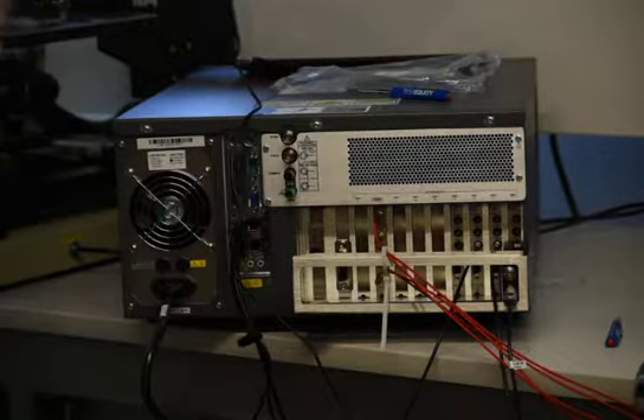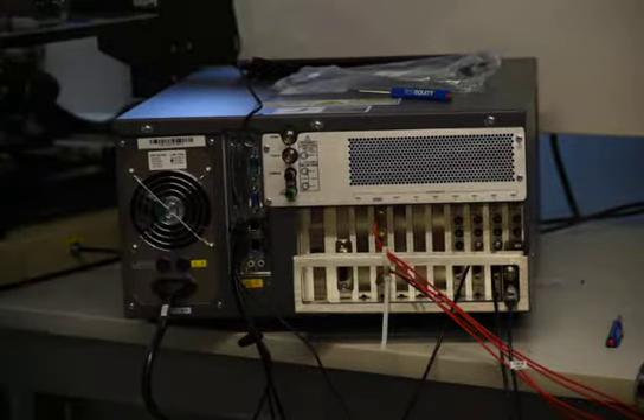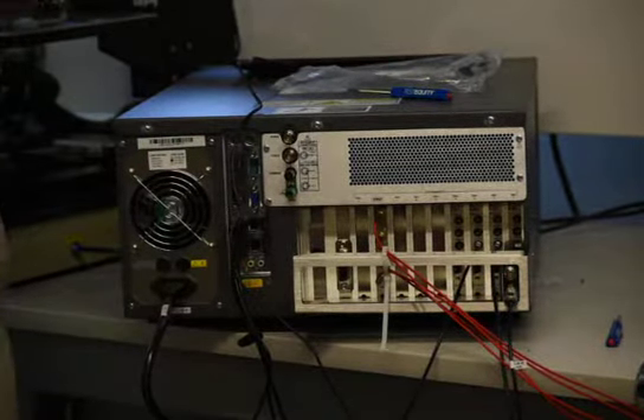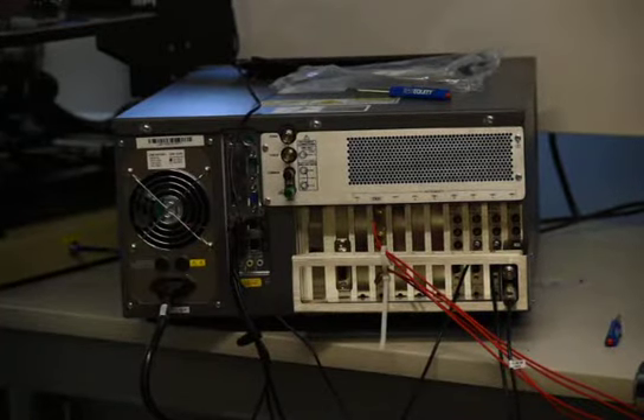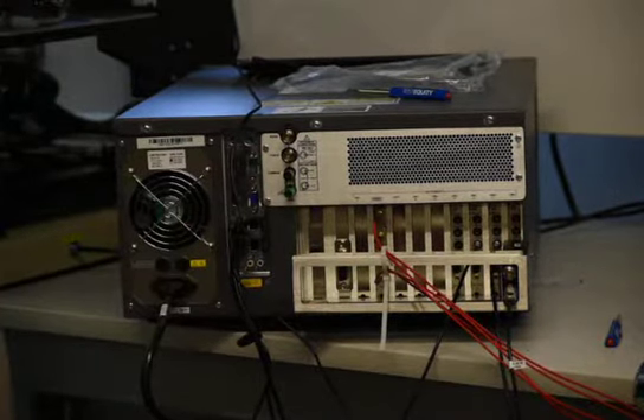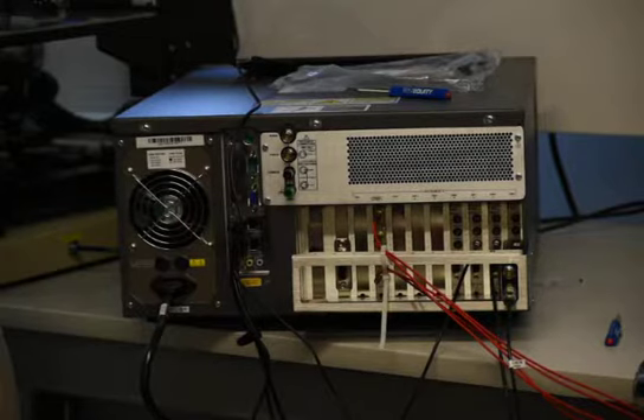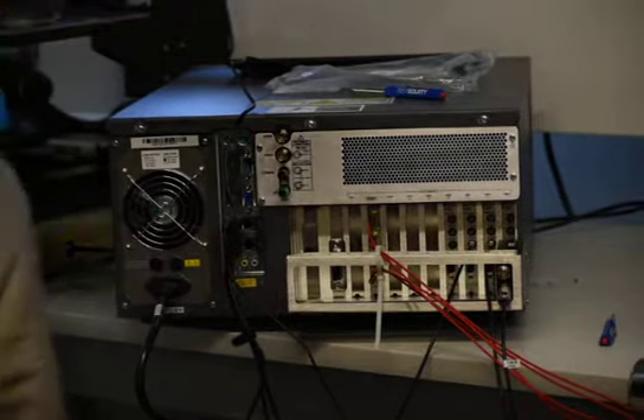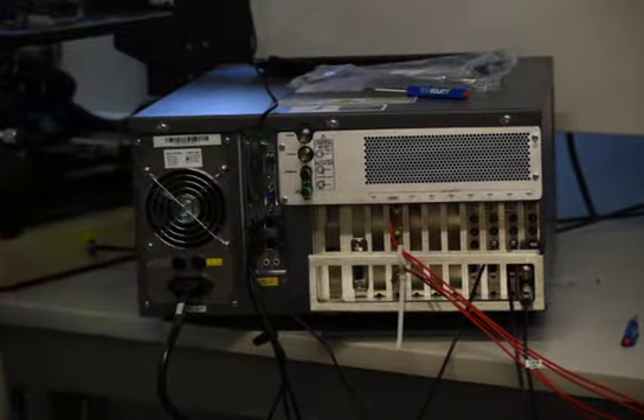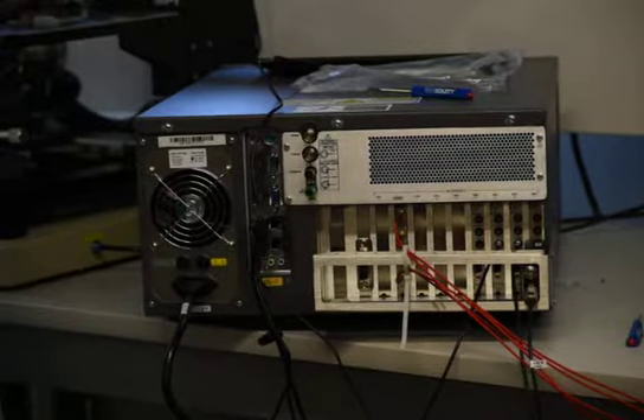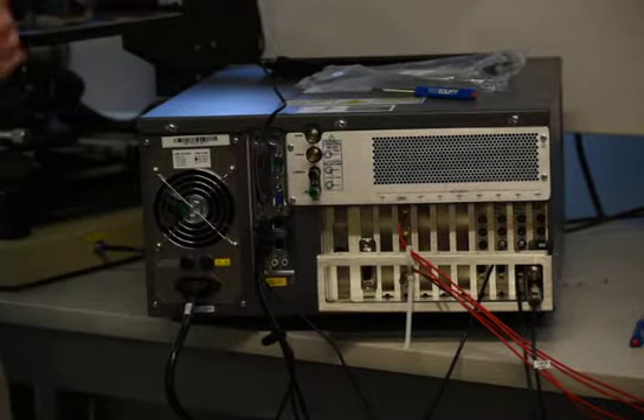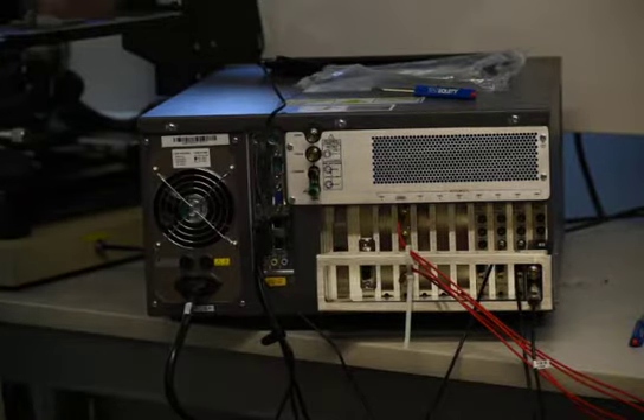So what a lot of people will do if they're doing a lot of high voltage is have a discharge probe that's got a resistance to ground. You ground it to a good ground, and you just touch your device with the probe before you contact it with your fingers. Just be aware, you don't want to use a dead short, because then it's a high energy spike when you hit it.